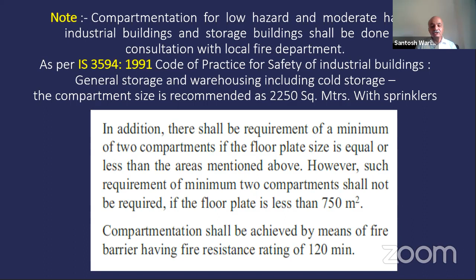There is again one standard, IS 3594, for warehousing and cold storage areas, where the compartmentation recommended is 750 square meters. But if you are going with the sprinkler system, it can be extended up to 2,250 square meters. So this is the requirement from the individual standard. We have already seen the compartmentation requirement of 750. But if the floor plate is only 750, then you should not divide it into two compartments as per the code requirement. Then you can have a single compartment of 750 square meters. And all the components of the compartment should have a minimum fire resistance rating of 120 minutes.